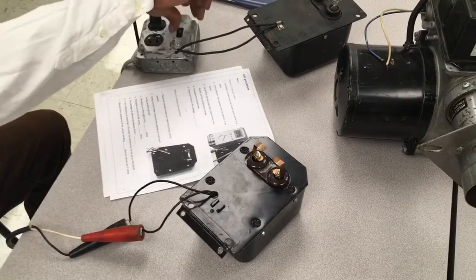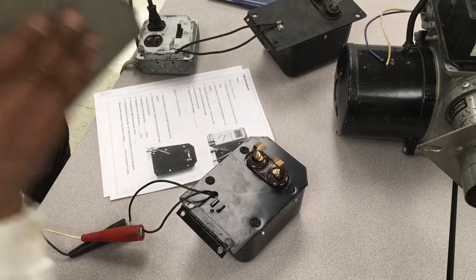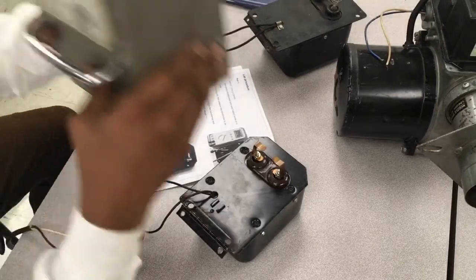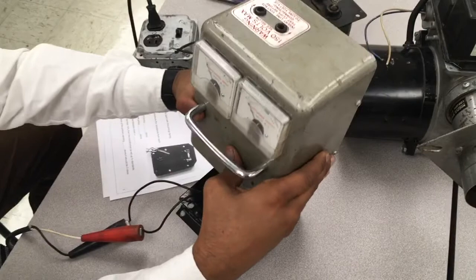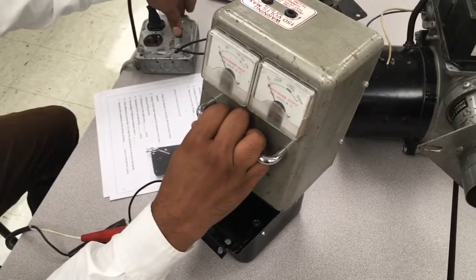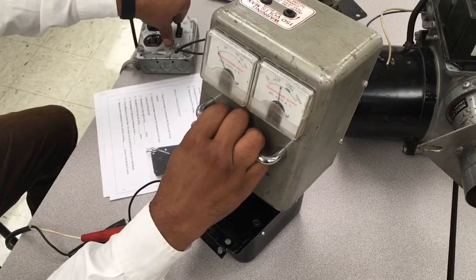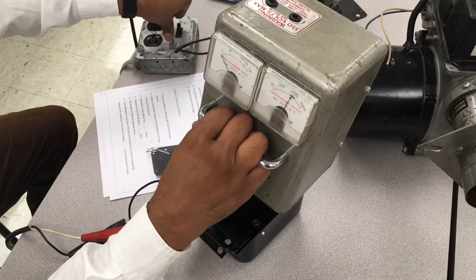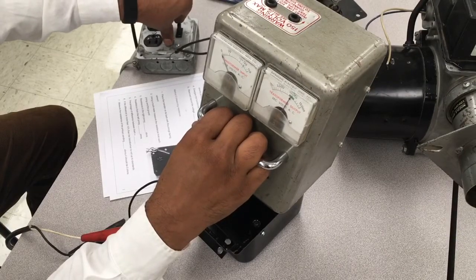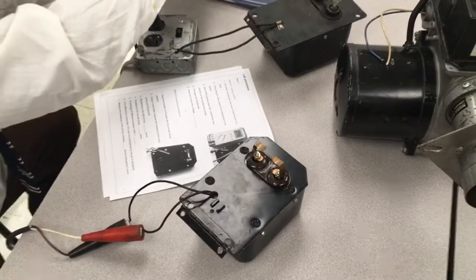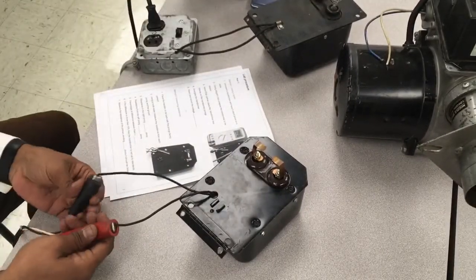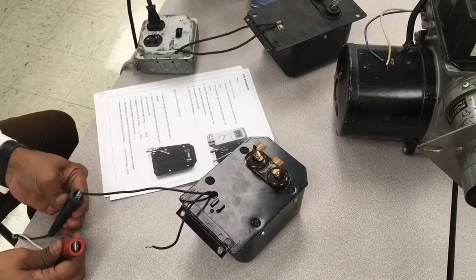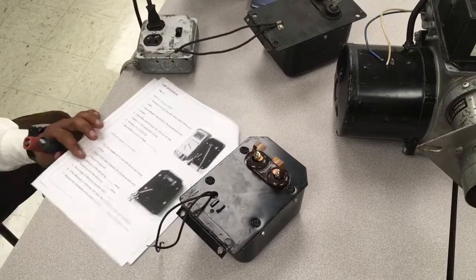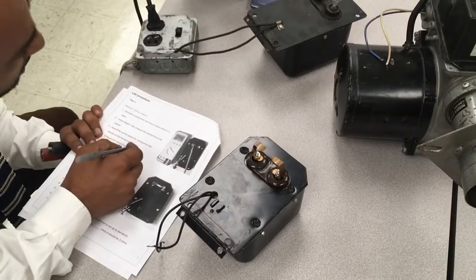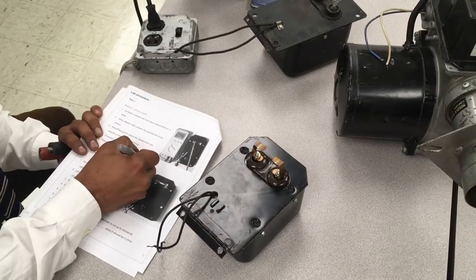This thing is pretty heavy, so make sure you place it correctly and be ready for the reading. I'll turn it on, see how it sparked a little bit. Actually, I'll turn it off. First, I'll place these on the lead and I'll turn it on. As you can see, it's stable at 10,000 volts exactly. Okay, so this is the best and easiest way to test a transformer if you have this big piece of machinery. If not, then you will move on. So here we got right on the spot 10,000 volts.